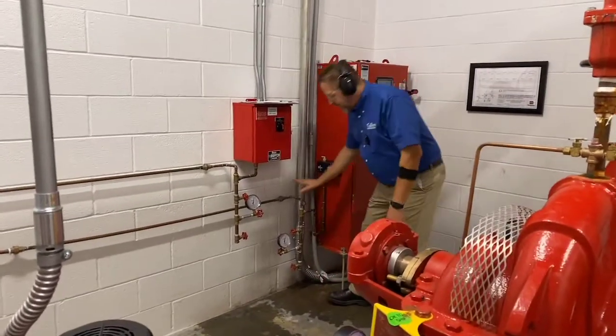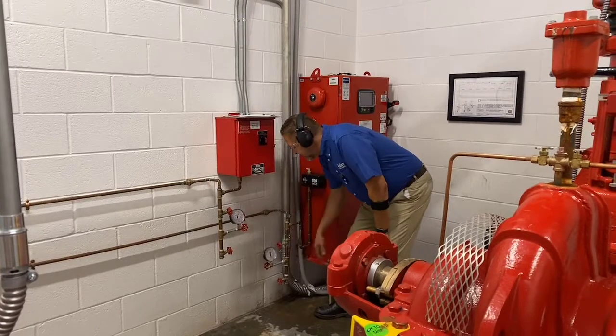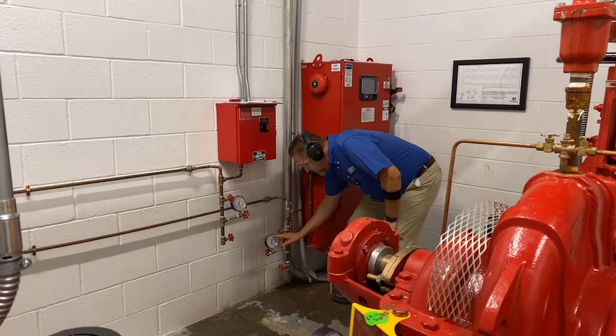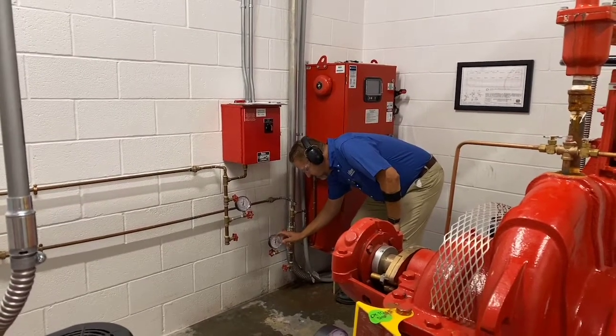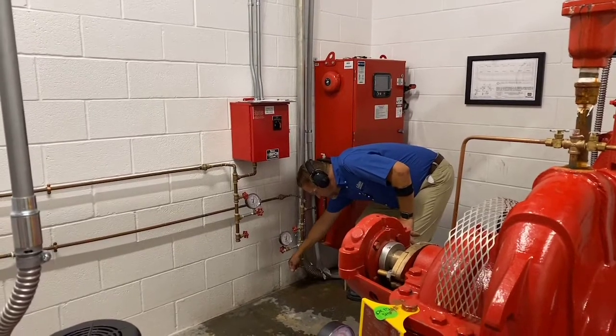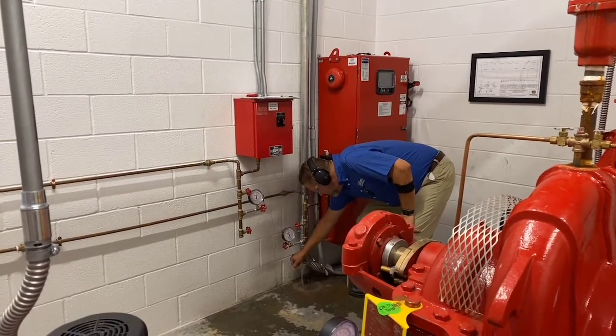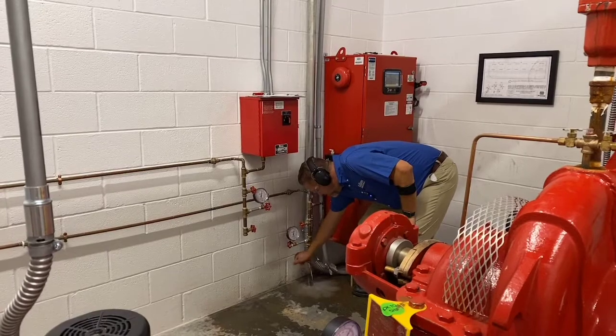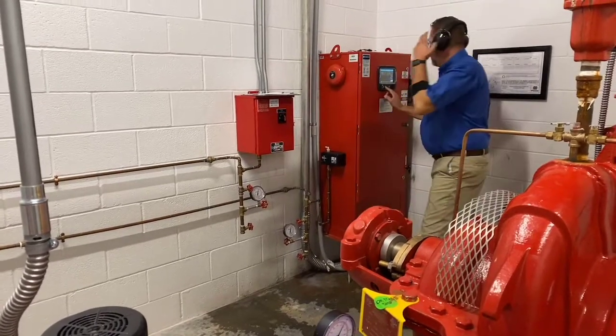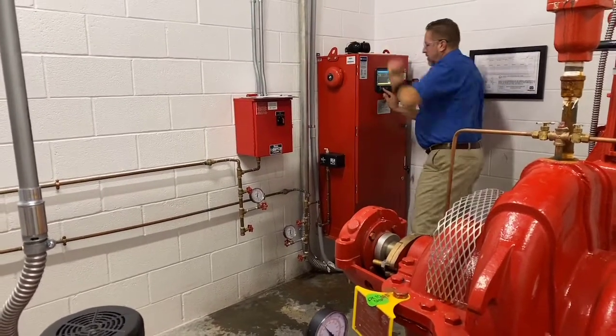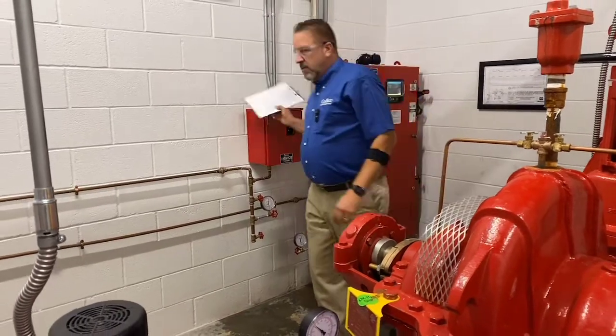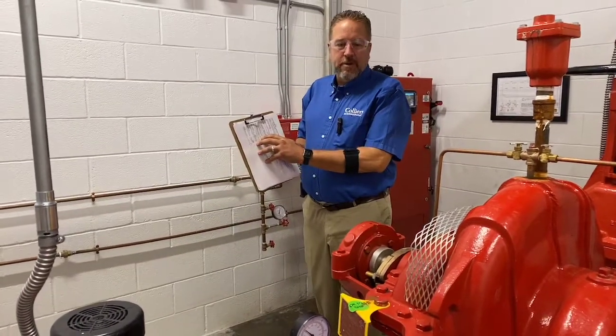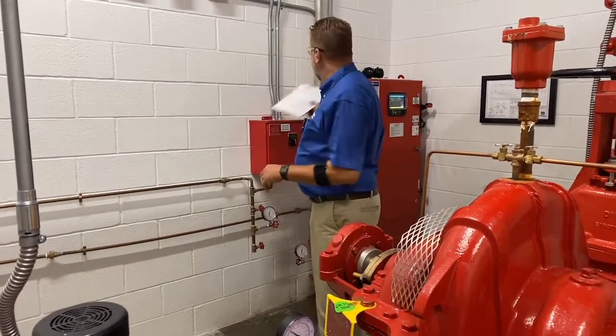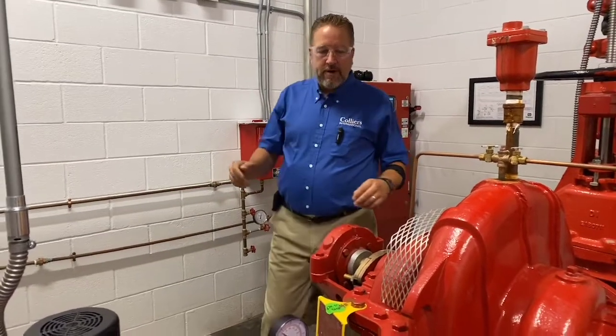Over here at the fire pump controller, you've got your pressure sensing line. Got a gauge here. You're going to watch it fall. Look at the pressure where the pump starts. What you're going to do with that is note that pressure, and also these gauges here and some of the other stuff that's required.